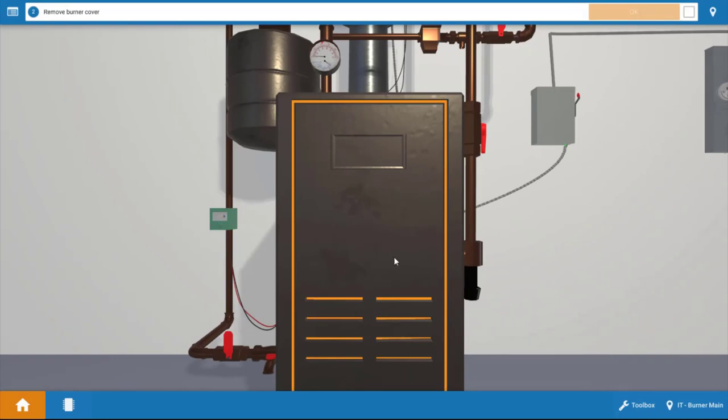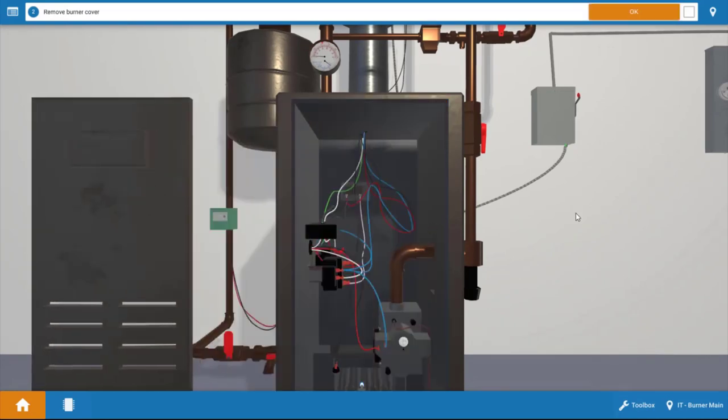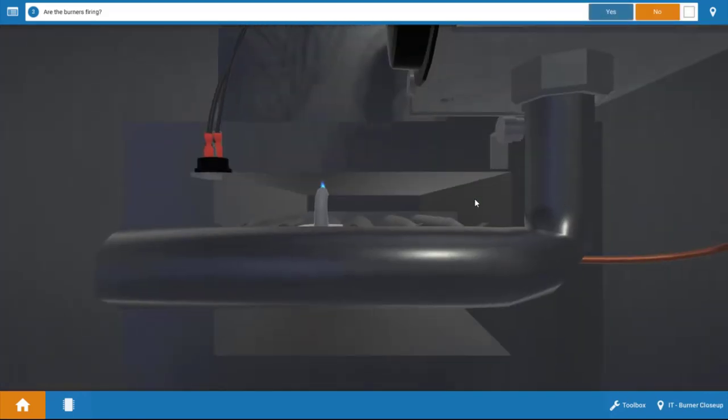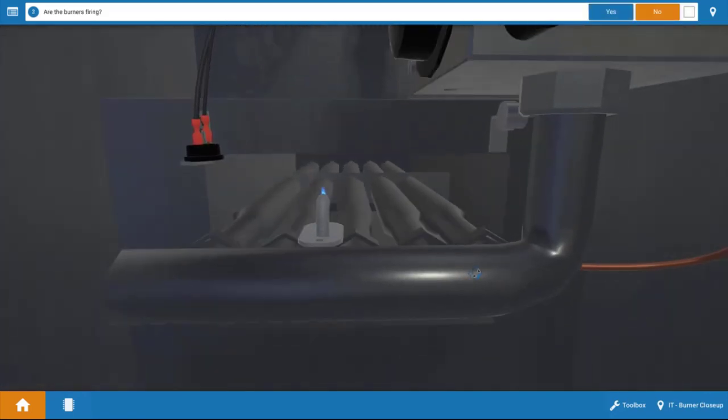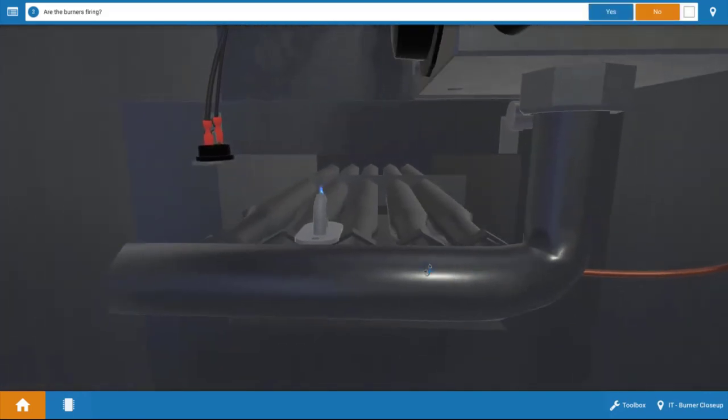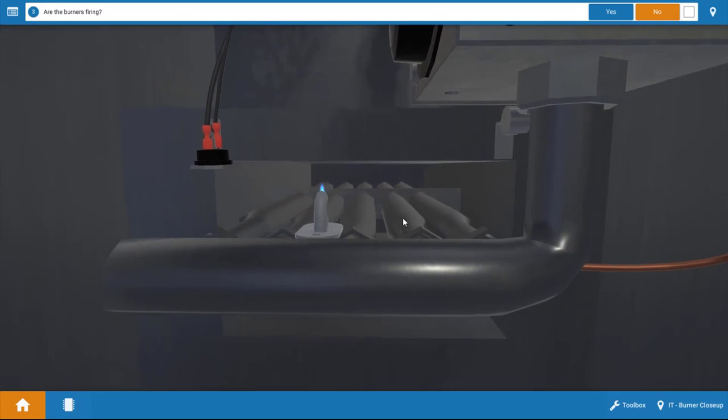Next, we need to remove the cover from the boiler and take an inventory of which loads are operating. So now that we've done that, we're clicking OK, and if we look in, we can see our burners are not firing here. We do have a pilot flame, but there's no burners, so we're going to click No here.